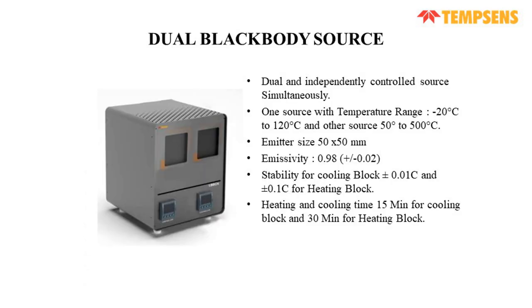This is, like we discussed, the dual dry block. This is the dual black body source. So in the dual black body source, one will be a cooling section, and one will be a heating section. Both sections are incorporated in a single body, so they are dual and independently controlled sources simultaneously. One source has a temperature range of -20 to 120 degrees centigrade, and the other is 50 to 500. So we offer this from -20 to 500 in a single body.